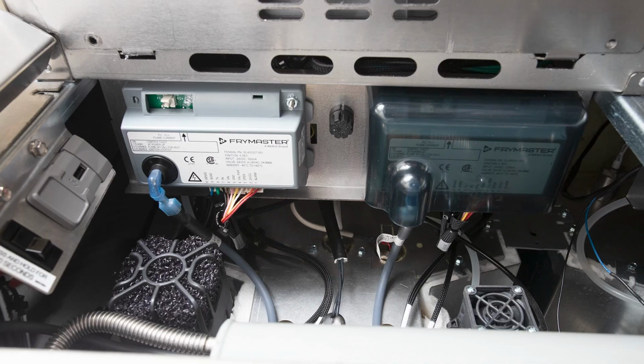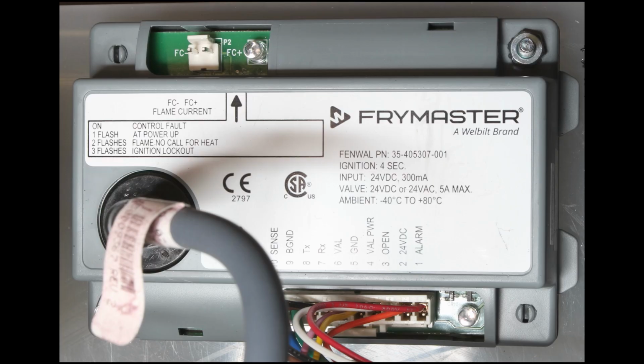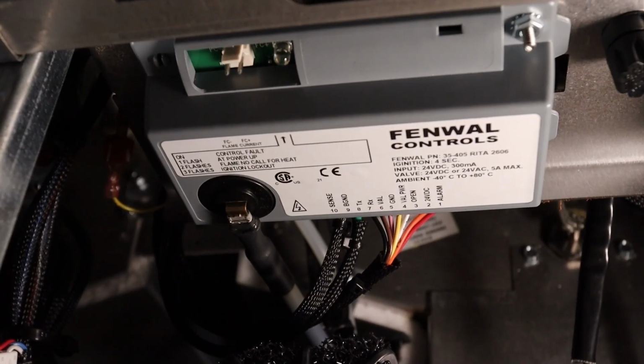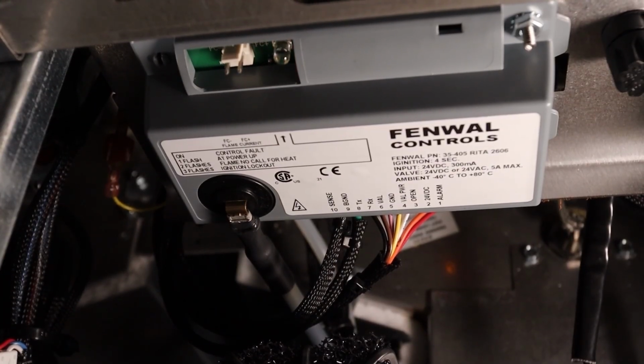The spark modules mounted under the controllers of the Intuition Fryer have LEDs that can be used for diagnostics. They are shown here with and without a protective cover. The LEDs show electrical activity in the circuit. This one flashes in red and shows latch circuit activity or a failure to sense flame. This one flashes in green and shows 24 volts DC is available at the module. One red flash means the latch controller has closed. The module is ready for a call for heat.